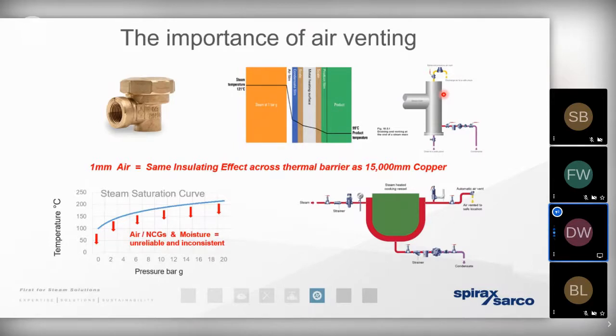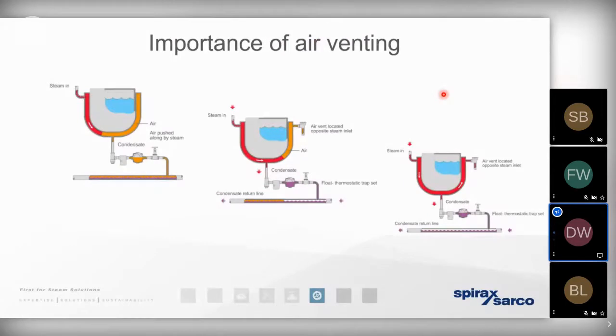So just to take that one step further, I want to show you the example of a typical process here. Now, on this occasion, we're looking at a jacketed vessel, but it could easily apply to any other heat exchanger, such as a shell and tube or a plate heat exchanger. Certain steam trap types have got the capability of being able to vent away not only condensate, but also air, especially when the system is starting up from cold. And that's a huge benefit, because the more air we can vent away, the quicker we can bring the process up to temperature. So the primary purpose of a steam trap is to vent condensate away.